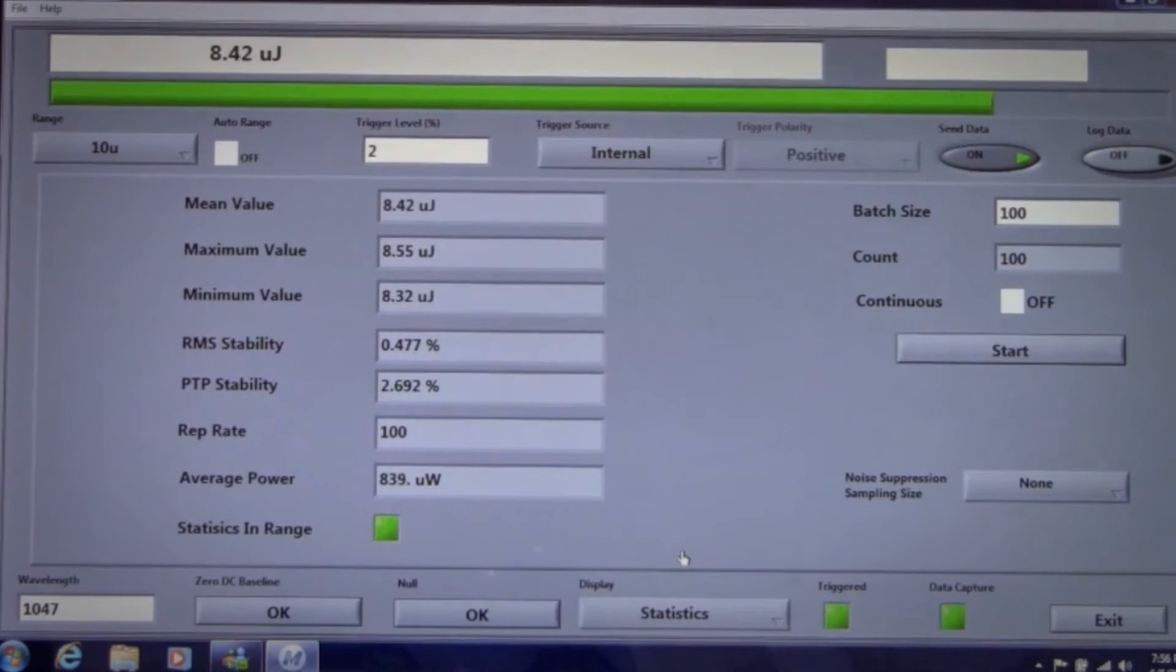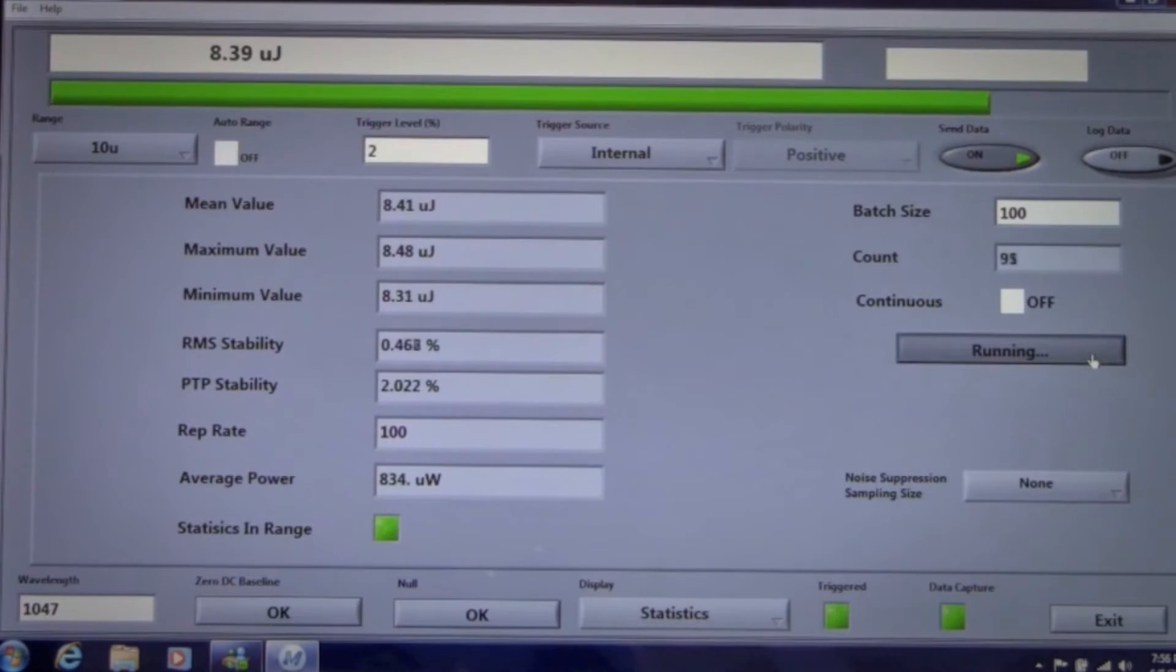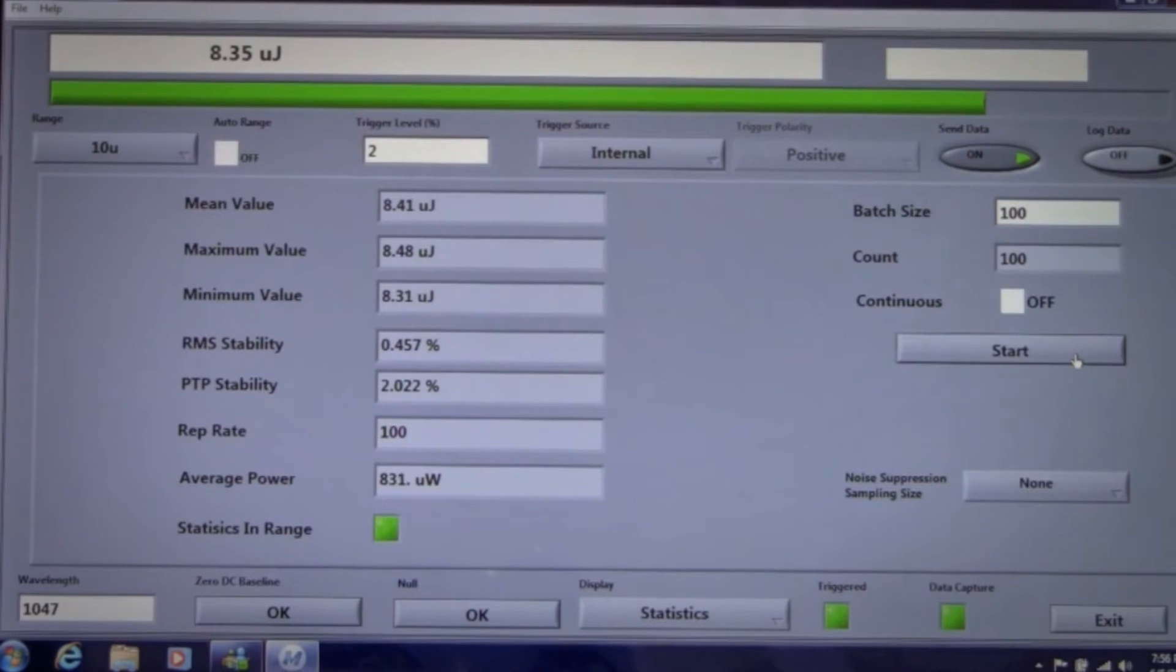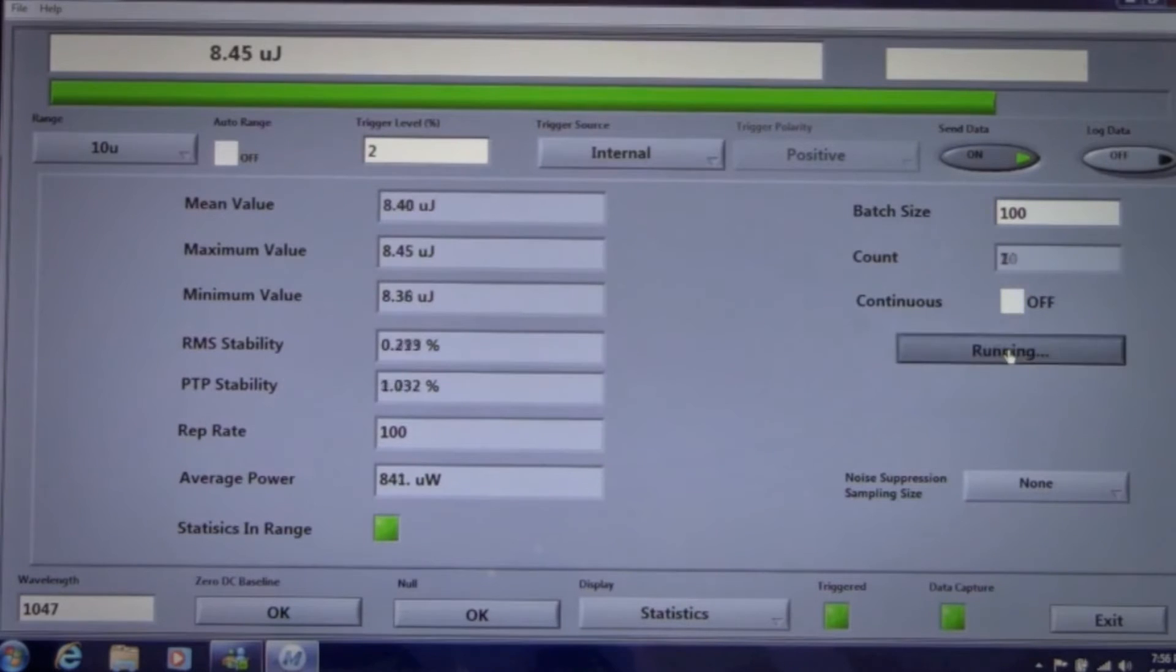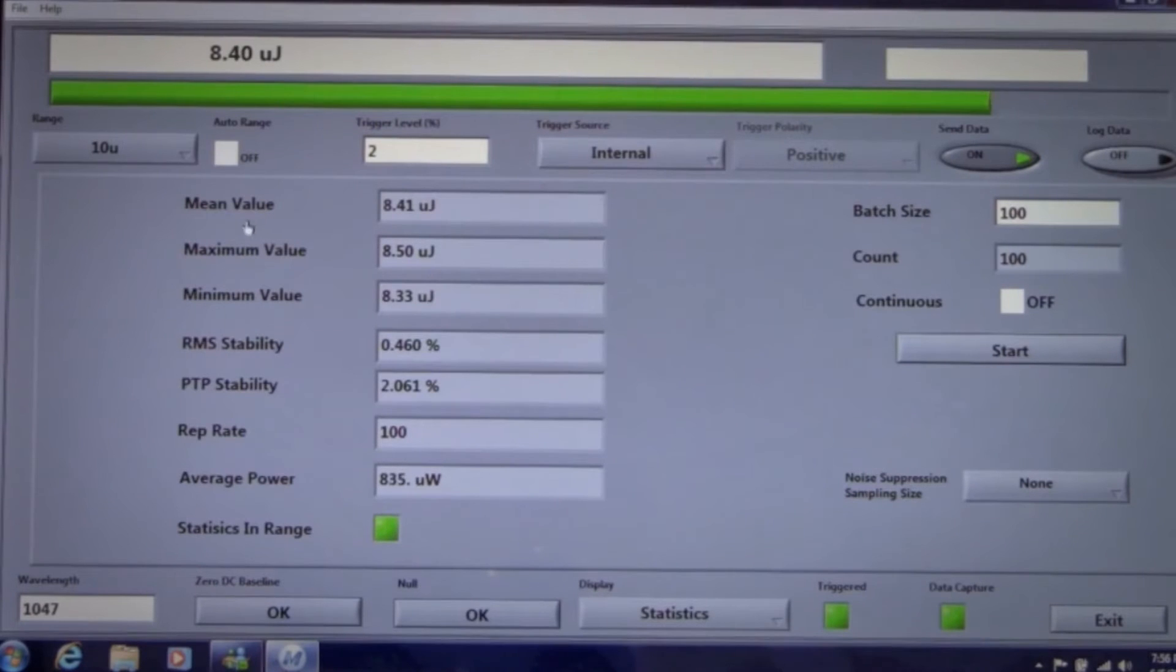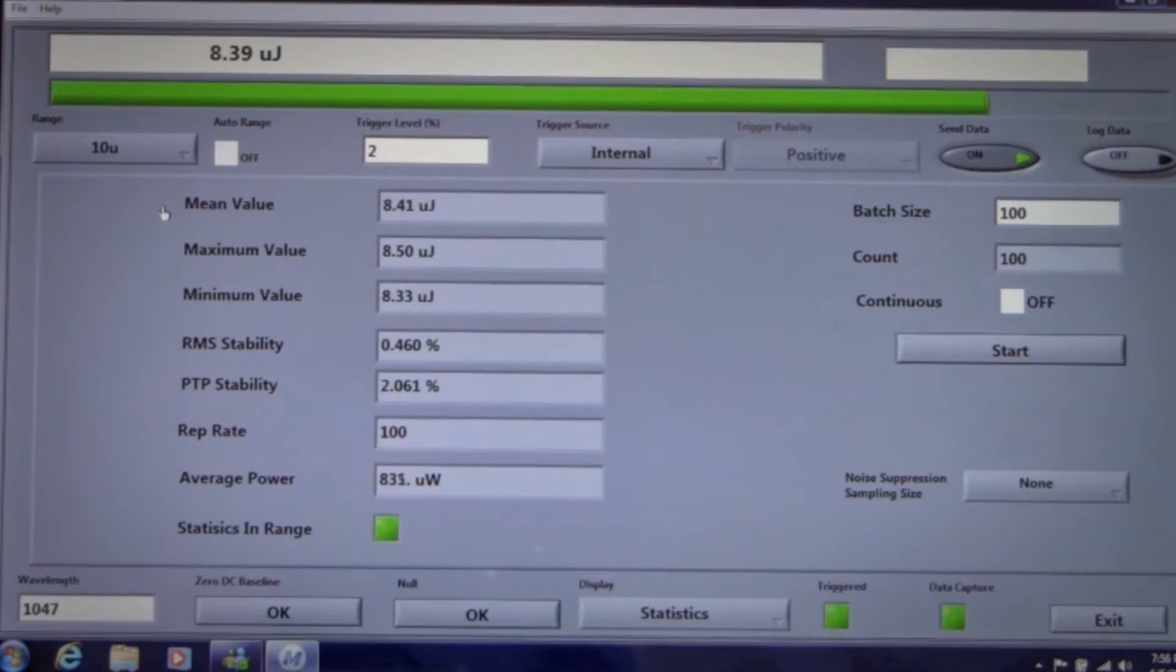Statistics, we've saved the best for last, the powerful diagnostic statistics screen. You can capture and display pulse energy statistics continuously or in a defined batch size. We're measuring the pulse energy of our YLF laser running at 100 pulses per second and reading about 8.4 microjoules. Let's take a look at our batch of pulses.